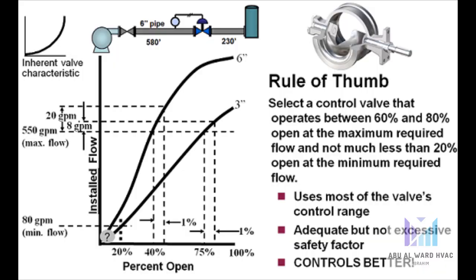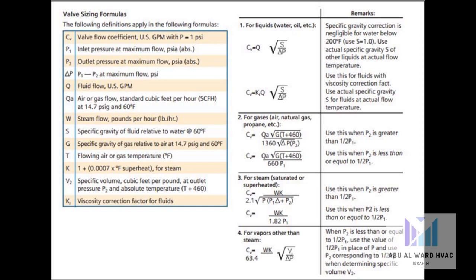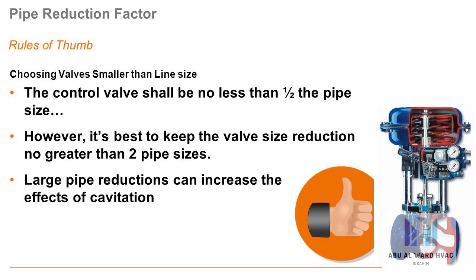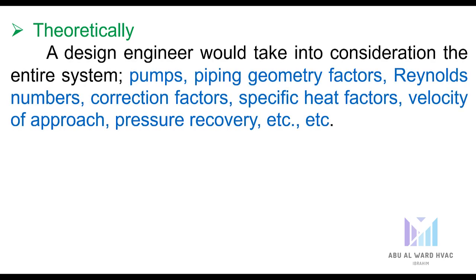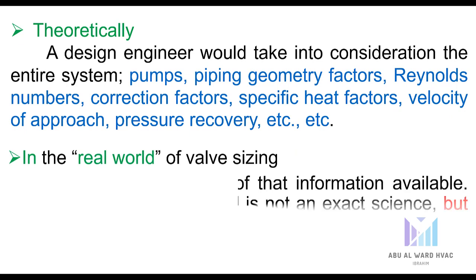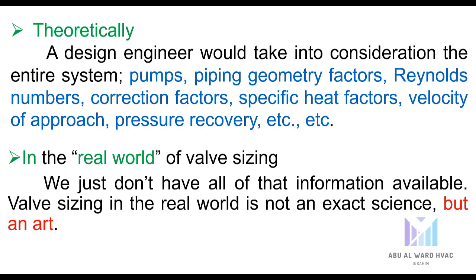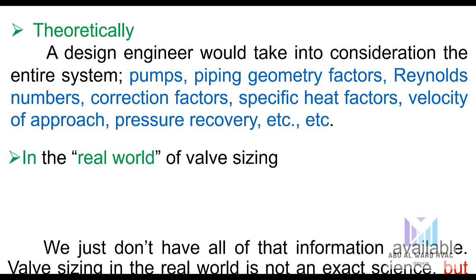A control valve is the single most important element in any fluid handling system, and selecting the proper valve will have a great effect on the efficiency of the system. There are volumes of information on the science of valve sizing and fluid mechanics. Theoretically, a design engineer would take into consideration the entire system: pumps, piping geometry factors, Reynolds numbers, correction factors, specific heat factors, velocity of approach, pressure recovery, etc. In the real world of valve sizing, we just don't have all of that information available — valve sizing is not an exact science but an art.